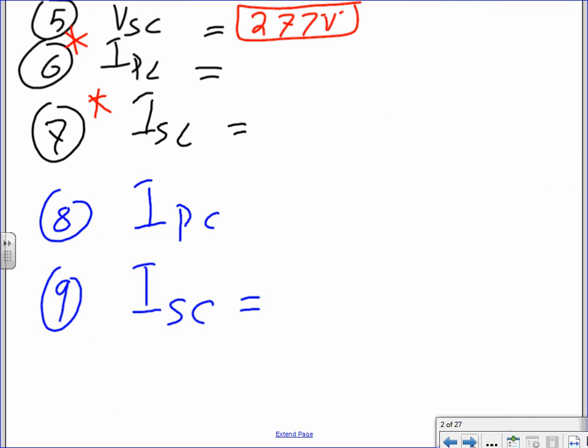Okay, so now let's go find the I primary line. Guys, piece of cake. You take the kVA, which is 225 kVA, divide it by 1.73. Everybody understand why 1.73? That's a component of the three-phase system. And what's the primary voltage, gentlemen? Line to line, 13.8 K. When you do a problem like this, Adam, the easiest way is to cancel the K with the K, right? You guys can see this, the K's cancel with each other, right? Because kVA over kV becomes 225 divided by 1.73 multiplied by 13.8. Because there's K at the top and the bottom, these cancel with each other. Gentlemen, you got yourself a healthy 9.4 amps.